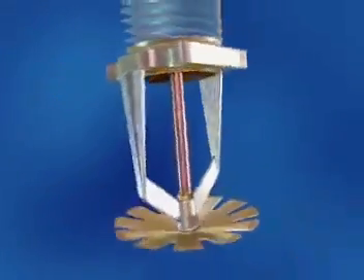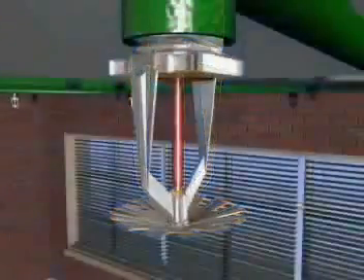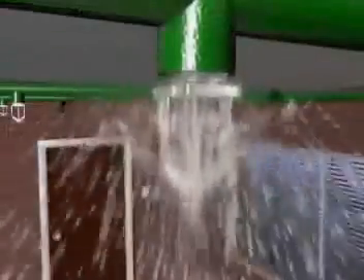Further increases in temperature cause a rapid build-up of pressure sufficient to shatter the bulb, releasing the valve seal and allowing the water to flow onto a water distribution system.